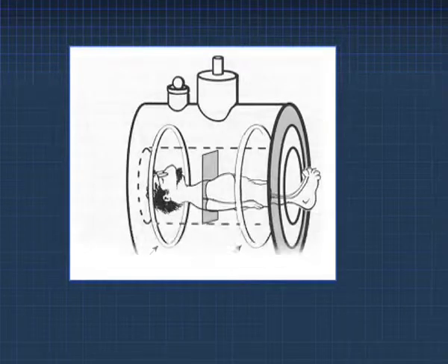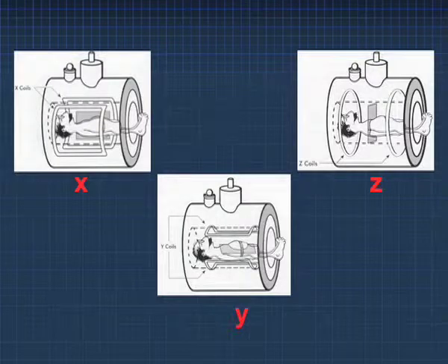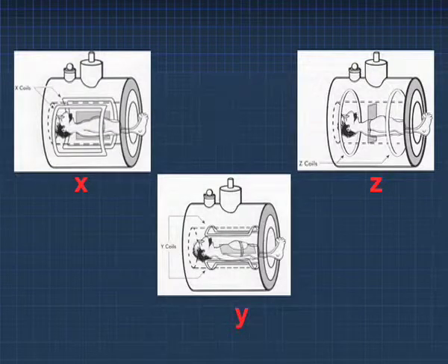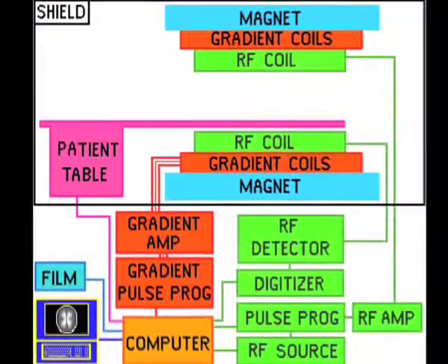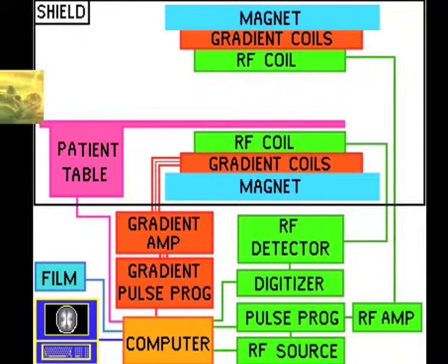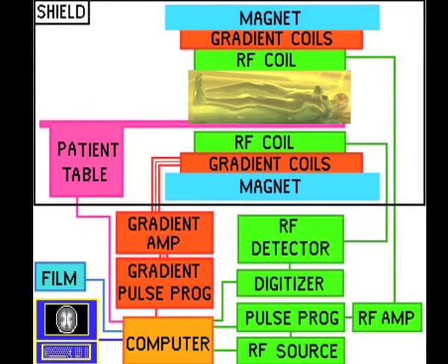The set of gradient coils for the Z axis are Helmholtz pairs, and for the X and Y axes, paired saddle coils are used. The RF coils are the antenna of the MRI system that broadcasts the RF signal to the patient and receives the return signal.